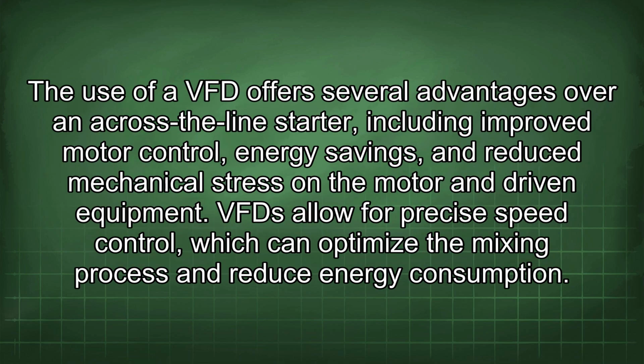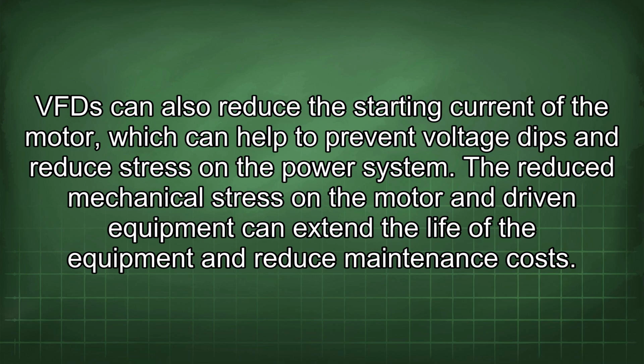The use of a VFD offers several advantages over an across-the-line starter, including improved motor control, energy savings, and reduced mechanical stress on the motor and driven equipment. The VFD allows for precise speed control, which can optimize the mixing process and reduce energy consumption. The VFD can also reduce the starting current of the motor, which can help to prevent voltage dips and reduce stress in the power system.